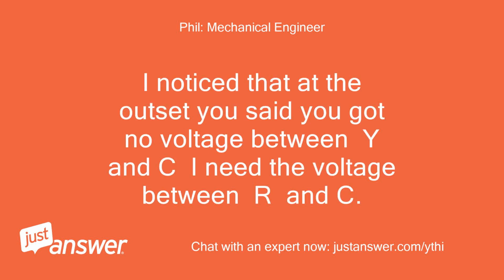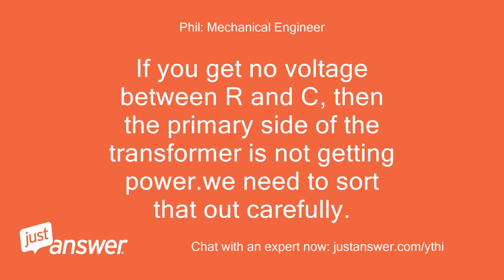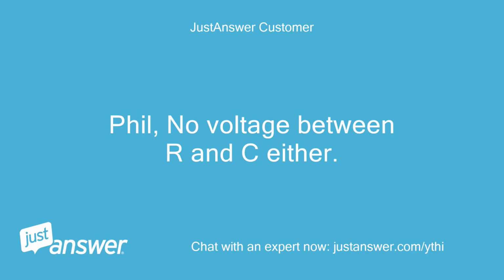I noticed that at the outset you said you got no voltage between Y and C. I need the voltage between R and C. If you get no voltage between R and C, then the primary side of the transformer is not getting power. We need to sort that out carefully. Phil, no voltage between R and C either.